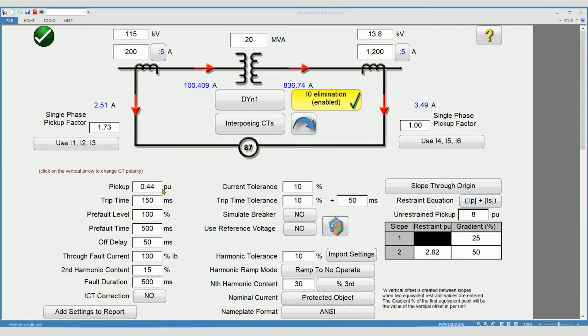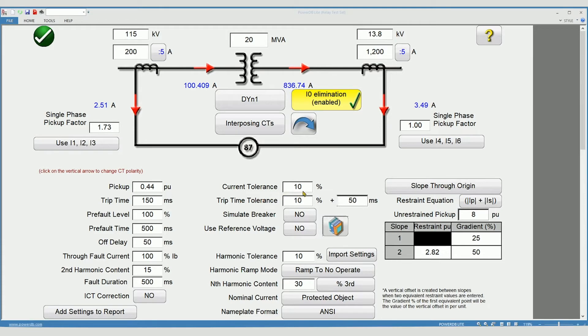Pickup is the minimum pickup threshold for your differential function and is expressed in per unit. Current tolerance is the allowable error for pickup.